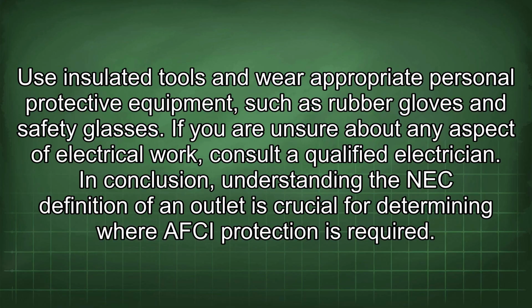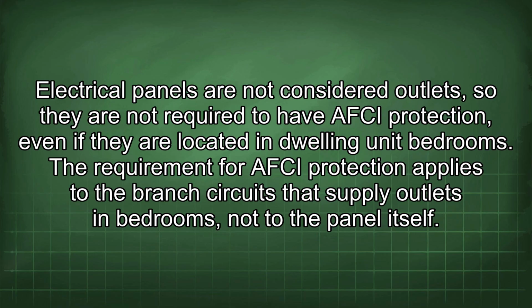In conclusion, understanding the NEC definition of an outlet is crucial for determining where AFCI protection is required. The electrical panels are not considered outlets, so they are not required to have AFCI protection, even if they are located in dwelling unit bedrooms. The requirement for AFCI protection applies to the branch circuits that supply outlets in bedrooms, not to the panel itself.